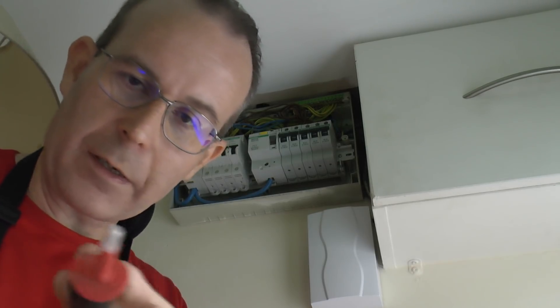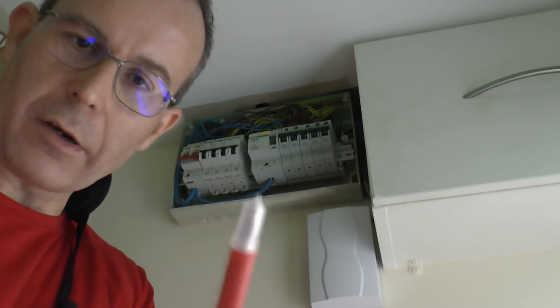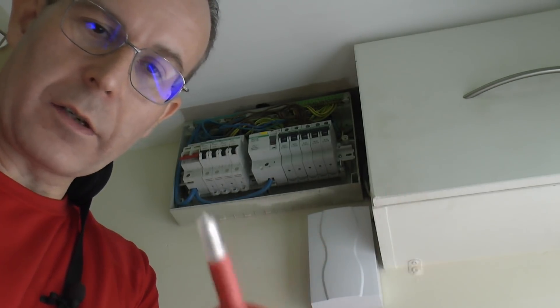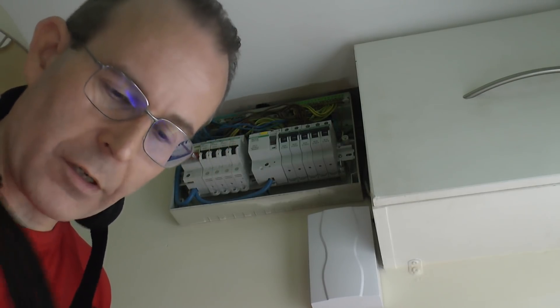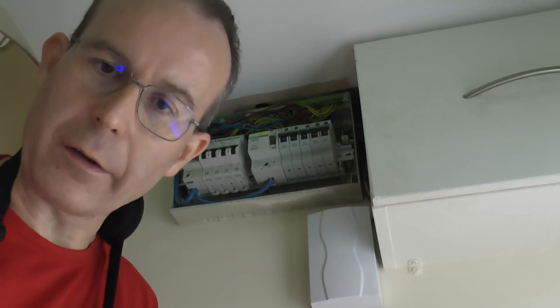Okay, well that's the test complete. It is important to press fairly hard on these to make a good connection on the terminal, particularly with these rather thin GS38 compliant ends. Of course some people might be tempted to remove those ends, but that's not really supposed to happen. So anyway, I have a result on the display here — let's have a closer look at that.